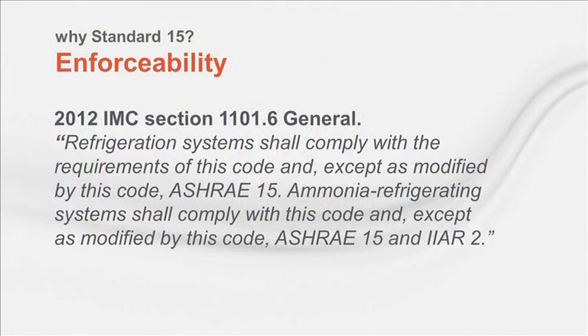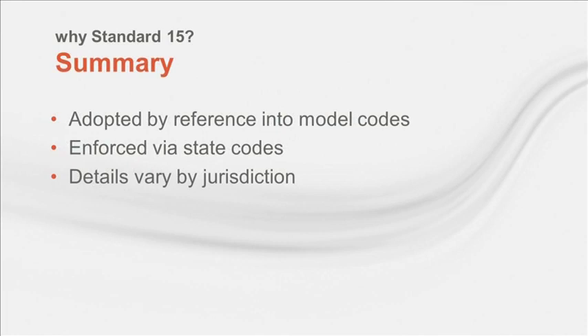For states that use the International Mechanical Code, the linkage between Standard 15 and the resulting code is really strong. Section 1101.6 of the IMC states, "Refrigeration systems shall comply with the requirements of this code and, except as modified by this code, ASHRAE 15." By this reference, all of Standard 15 is included in the IMC and the state codes that adopt it, unless the wording in the IMC conflicts with the standard. To summarize this first section, ASHRAE Standard 15 is not directly enforced, but it is included in part or in whole in most state codes. The process from standard to state code introduces the opportunity for variation, so it's essential to know the code details for the jurisdiction where the equipment will be located.